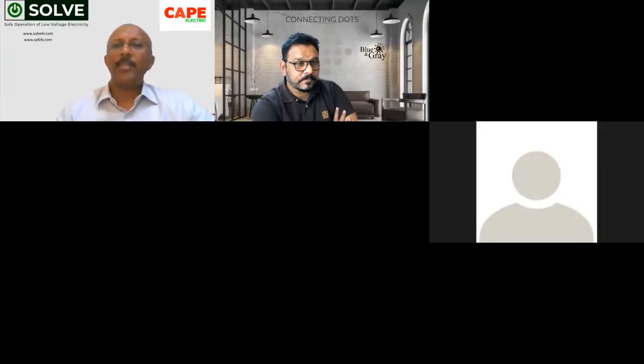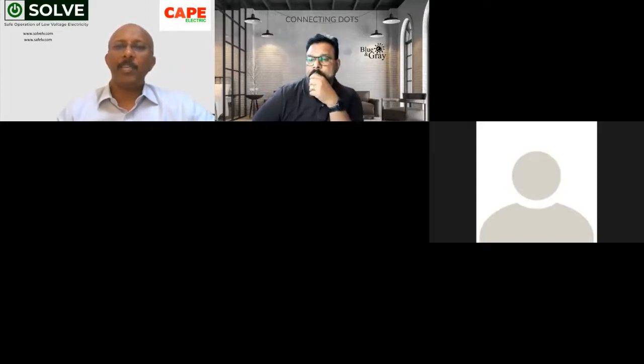There's an interesting question in the chat box from Mr. Ravindra Desai about the National Electrical Safety Code (NESC) by IEEE, which specifies best practices for the safety of electric supply and communication systems and has been in use for more than 100 years. In America there are two codes: the NEC, National Electrical Code, which applies within a building or consumer premise, whether industrial, residential or commercial; and the NESC, National Electrical Safety Code by IEEE, which applies to property belonging to the electricity supplier. But since India is a member of the IEC, we are supposed to follow the IEC standard, IEC 60-something, which was shown in the presentation.